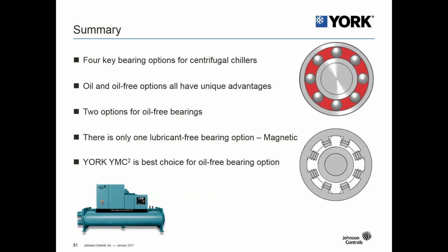So in summary, we went over the 4 different bearing options for centrifugal chillers, and we looked at oil and oil-free options, and they all have their unique advantages. There are 2 options for oil-free bearings. However, there's only one lubricant-free bearing option, and that's the magnetic bearings. And we feel that the York YMC Squared is the best choice for oil-free bearing operations.